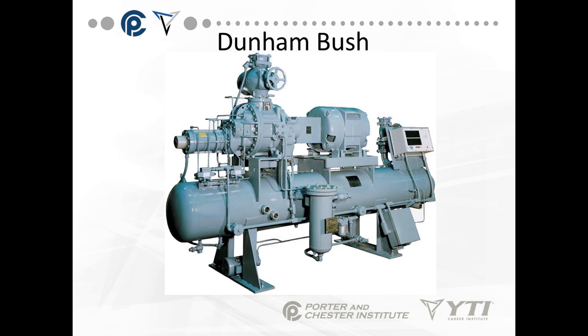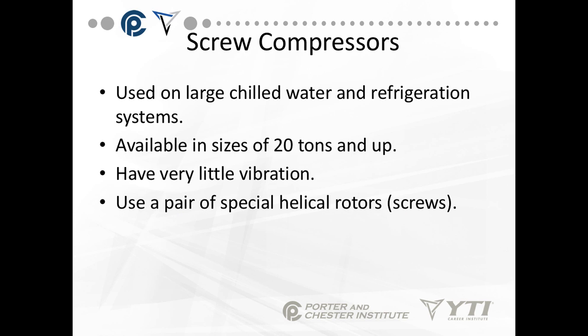Thus far we've talked about rotary and scroll compressors. The next type is a very large commercial unit — this is a screw compressor. It's used on large chilled water and refrigeration systems and is only available in sizes 20 tons and up. It has very little vibration and uses special helical rotors or screws to move and compress the refrigerant.